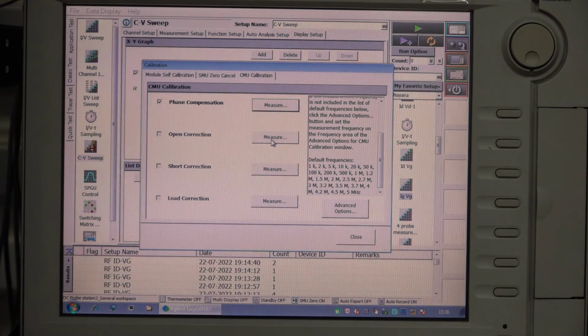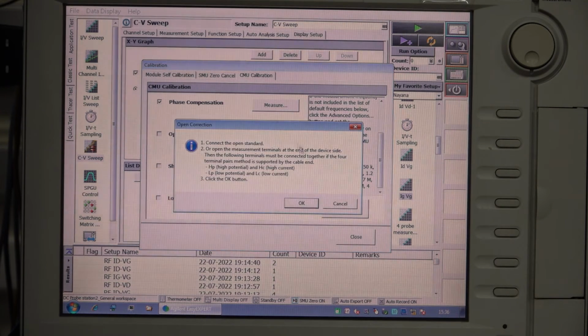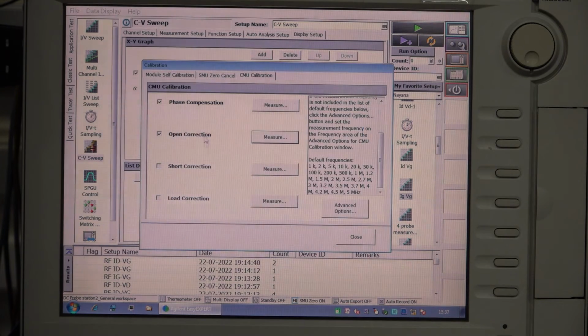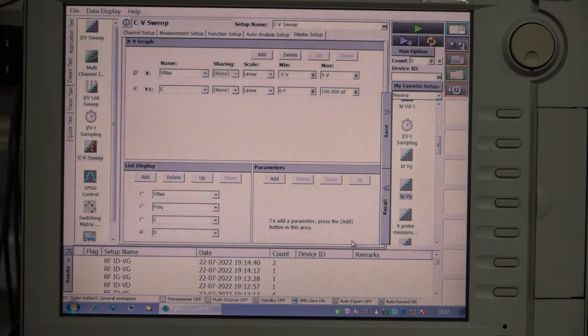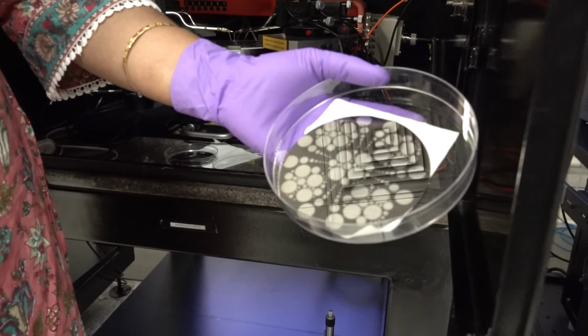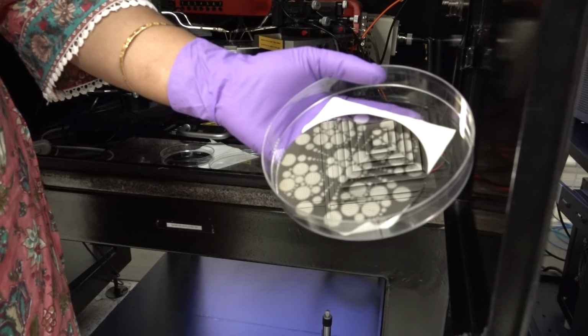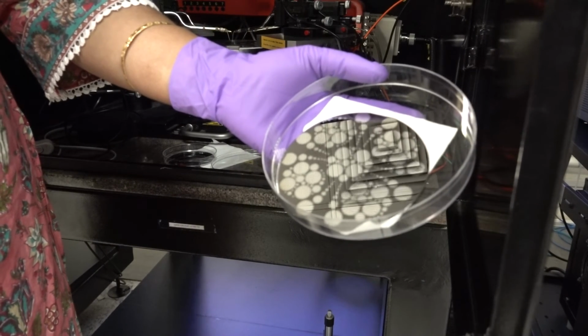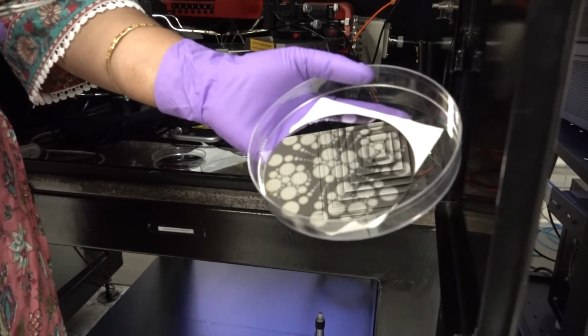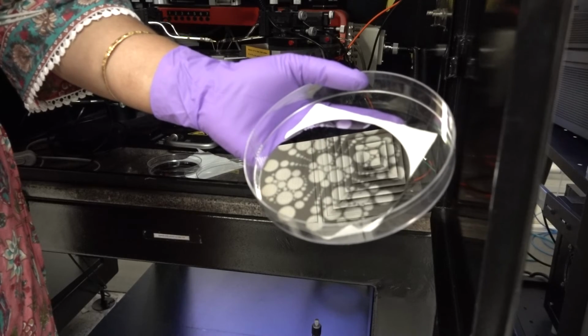Open correction can also be done. It's the same, it says a warning, so we are following the same. We have connected the short, high potential, high current, low potential, low current, and we have removed the device under test. So now the calibration is being done. We'll close and connect the device. This is the MOS capacitor, metal oxide semiconductor capacitor. I'll be probing this capacitor and I'll show you the demonstration.